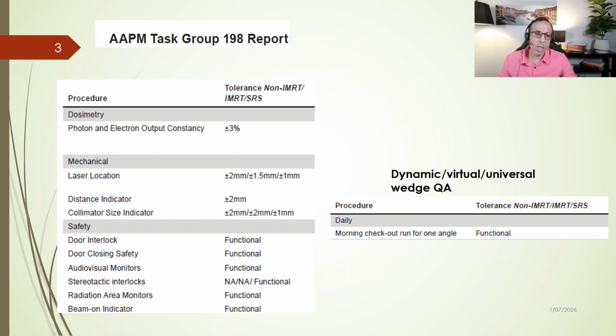We check the alignment of the room lasers, ODI or optical distance indicator, and collimation size. For conventional treatment, laser accuracy is typically required within 2 millimeters, while for high precision techniques such as SRS and SBRT, the tolerance is often reduced to 1 millimeter.